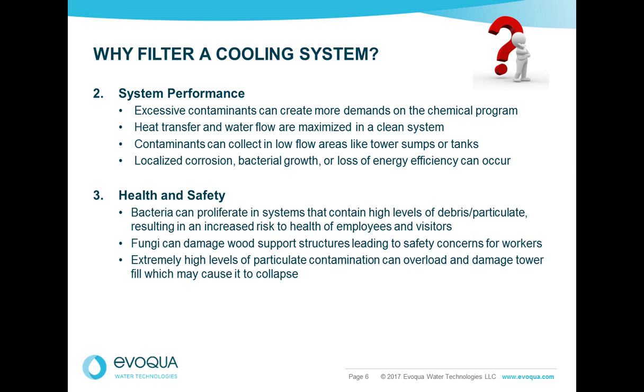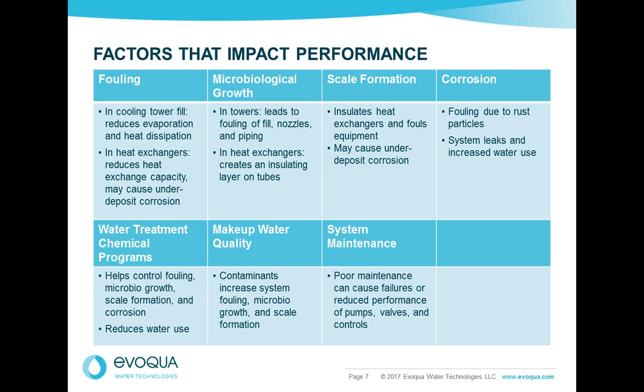System performance can be affected by the dirt. Excessive contaminants in the cooling water can increase your chemical demand. It can screw up the chemical system. It can affect heat transfer. Contaminants can collect in low flow areas. And also you've got an issue with health and safety. As I mentioned before, bacteria can affect people's health.